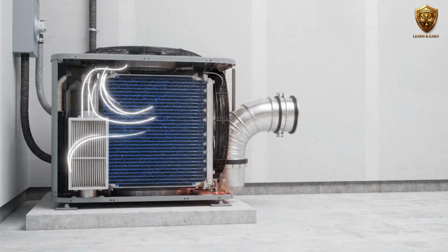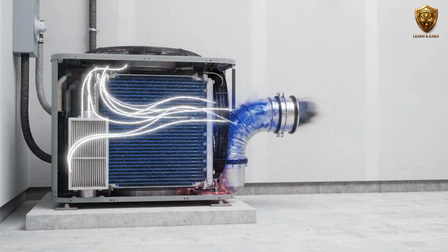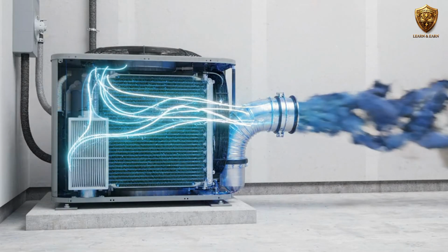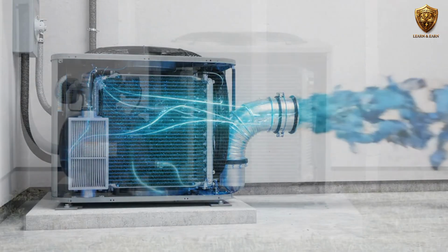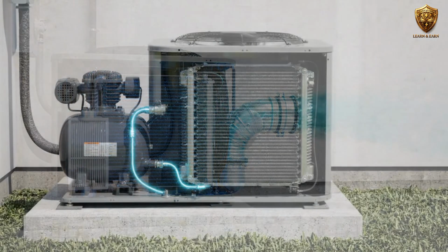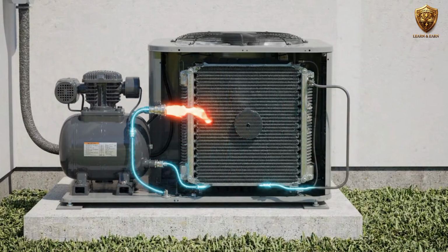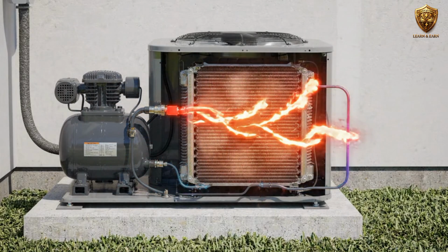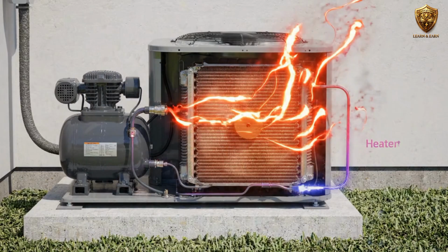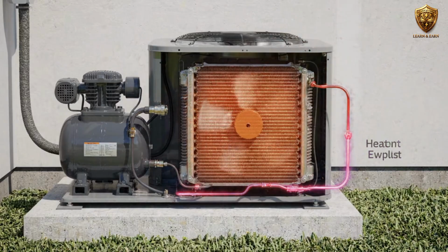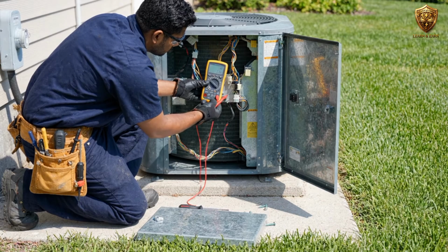If the system repeatedly trips a breaker, do not keep resetting it. A repeated trip is a warning that needs investigation. If a capacitor looks damaged, test it correctly before deciding what else may have failed. If the coil is frozen, find the reason for the freezing instead of simply removing the ice and restarting the system. And if refrigerant is suspected to be low, do not charge by guesswork. Find the evidence and check for the cause.